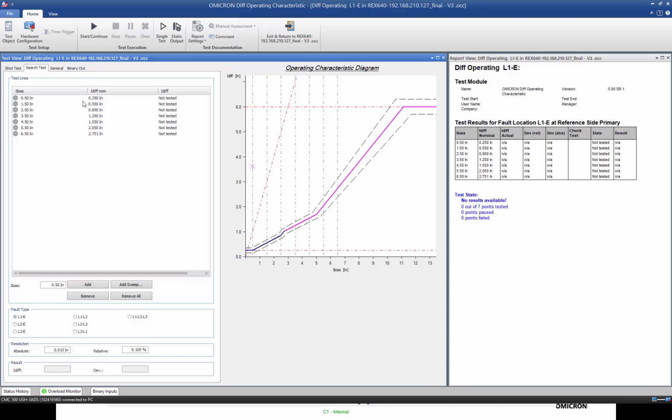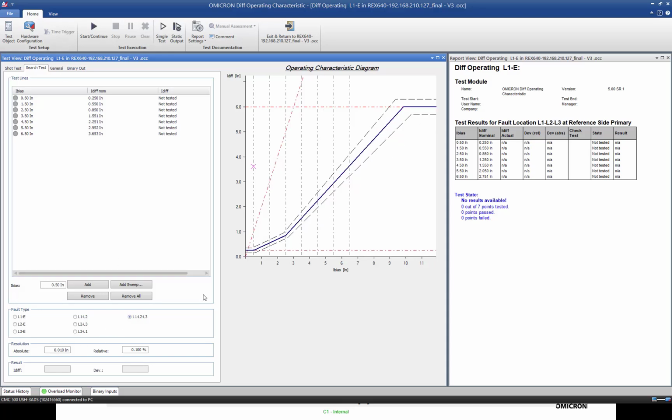So if you are choosing 3 line, you can see there is no effect of zero sequence elimination. But for single phase, the zero sequence elimination will appear. You don't have to check. It does it automatically. It will be automatically detected.